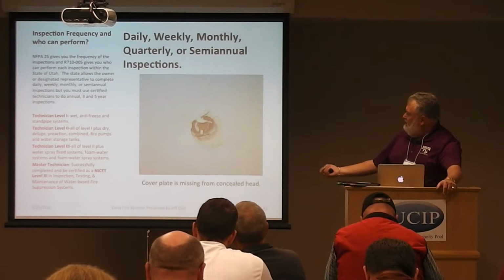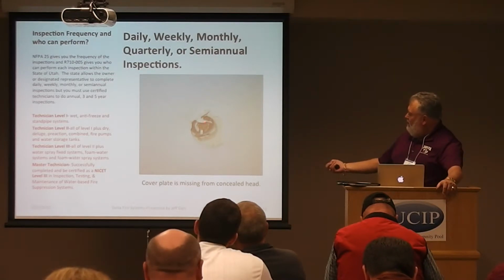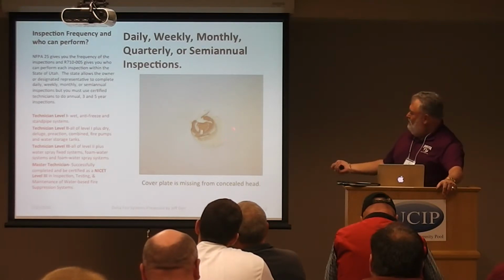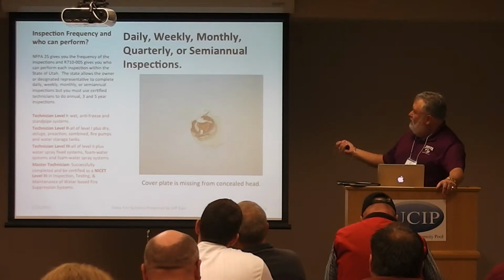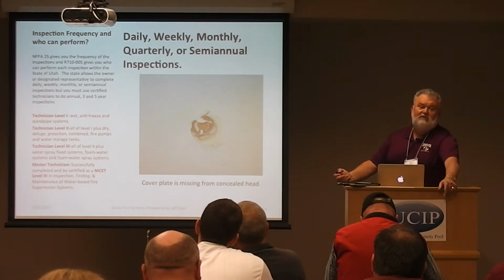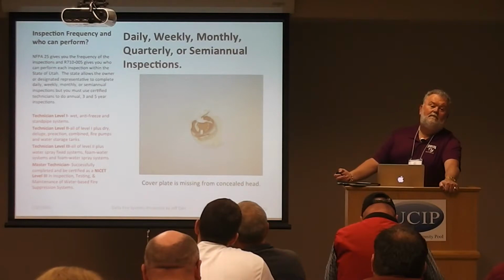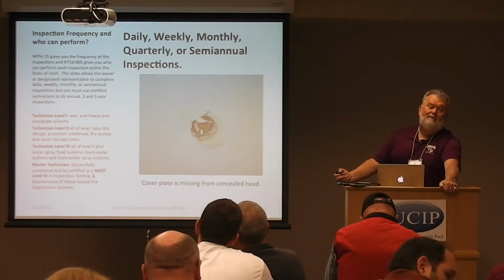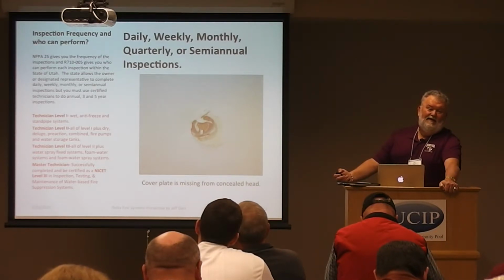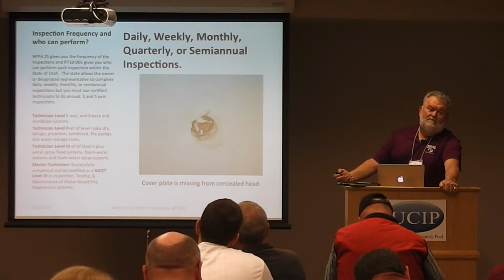Now, when you look at this here, this is a head right here. This is a concealed sprinkler head. The cover's been knocked off of it, going through and doing weekly inspections. Yes, sir. I have one of those in my jail, and the reason I have it off is that we've got it back on, but it's in concrete. That head is buried in concrete there. And so in order to get to it and get that other cover put on it, they didn't quite bring the sprinkler down far enough to screw that on it, so it's difficult. Prisoners like to mess with that too.